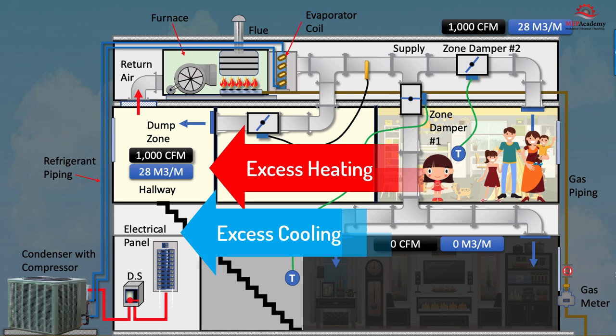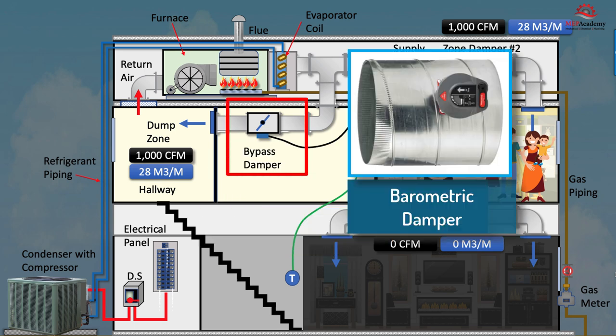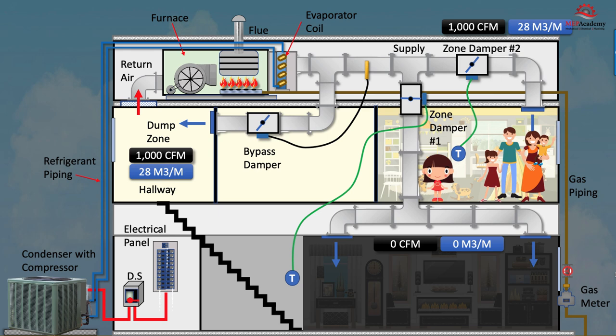We show a motorized bypass damper in this diagram, but a barometric damper is often used. The barometric damper is set to open when the pressure increases to a certain amount, allowing air to bypass the supply and be redirected to the return. Another option is to directly connect the bypass duct to the return duct, which avoids excessive temperature swings in a dump zone. There are many variations of this installation. The best system layout would be to have two separate HVAC systems — one for the first floor and one for the second floor.